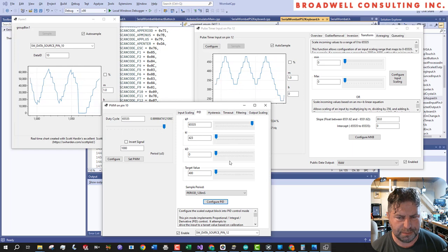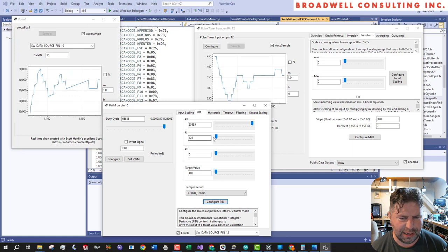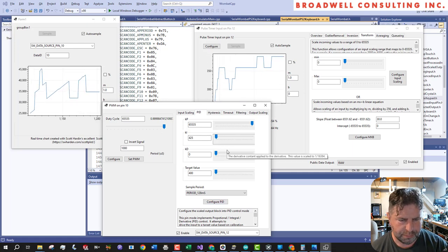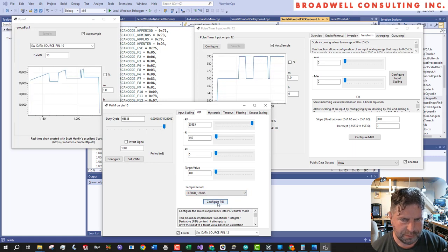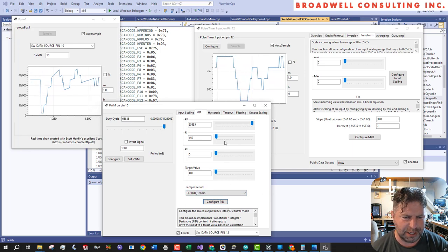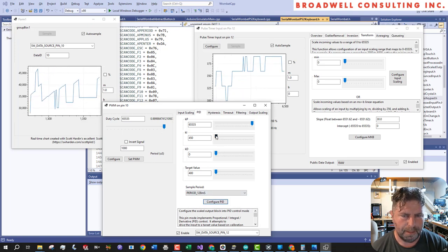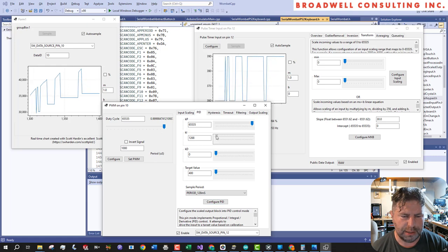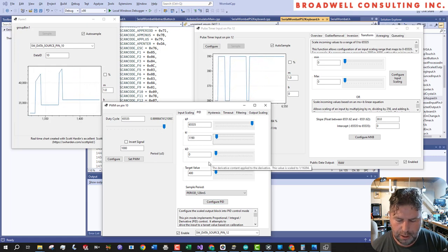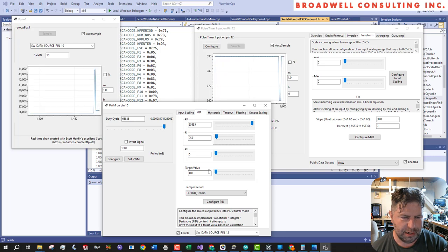So we'll reduce KI. And we're not quite getting up there as fast as I'd like. So let's make that one. We'll push it up to 500. Every time you hit configure PID, it resets the integrator. So it takes us a little bit of time to get back up there. Okay, and I'm going to make that, that's too much. I'll make that maybe 800.